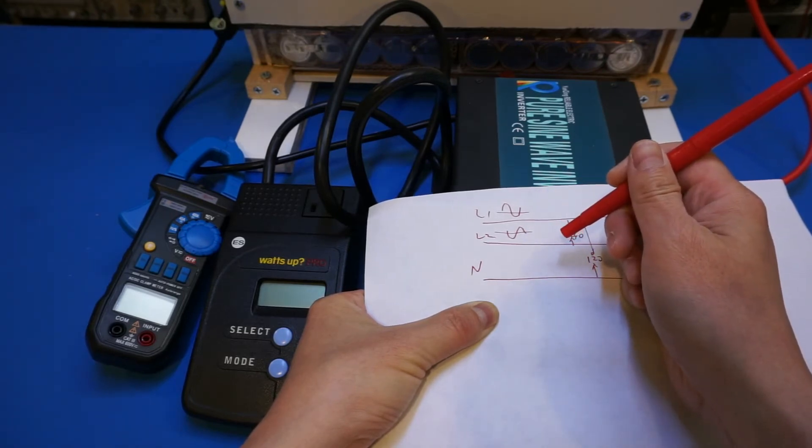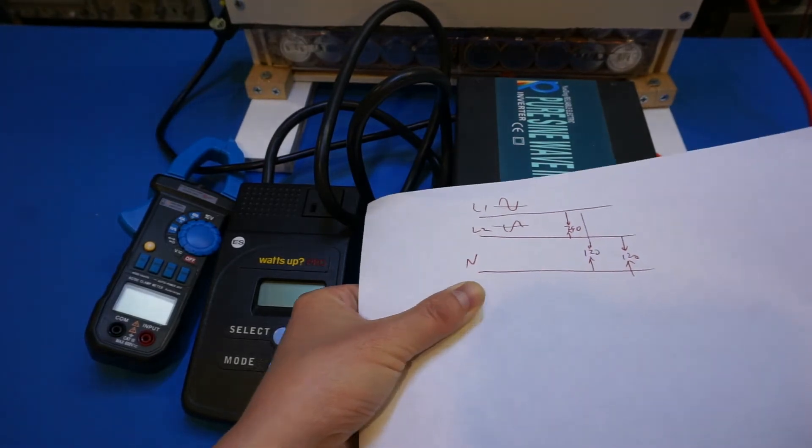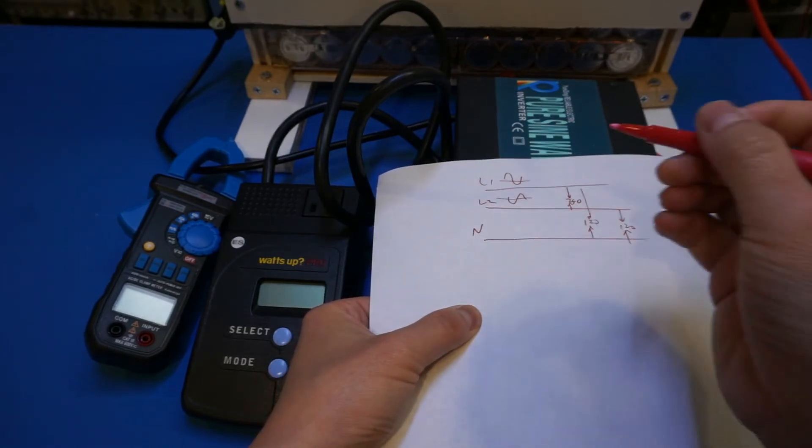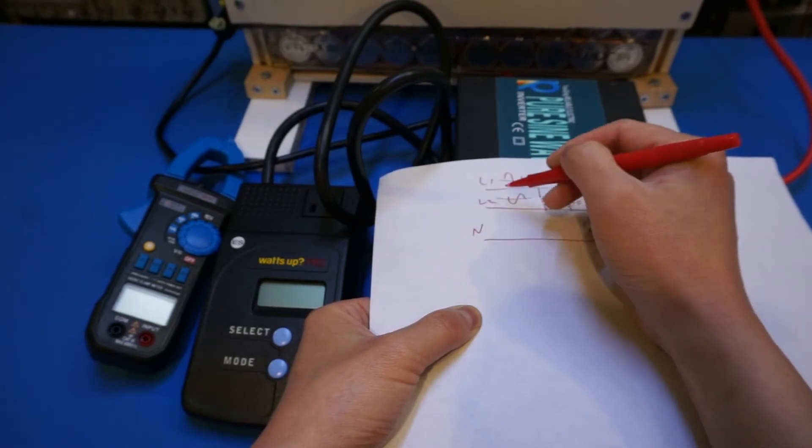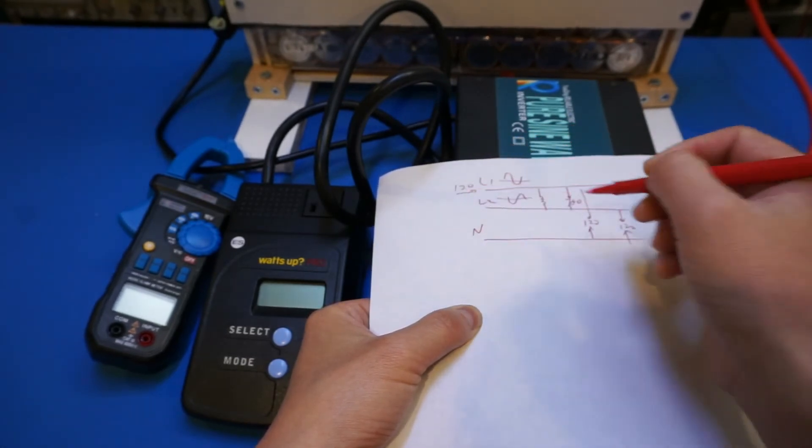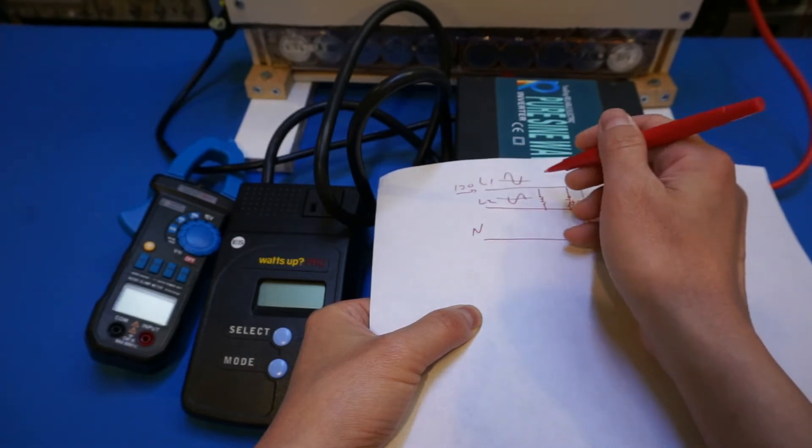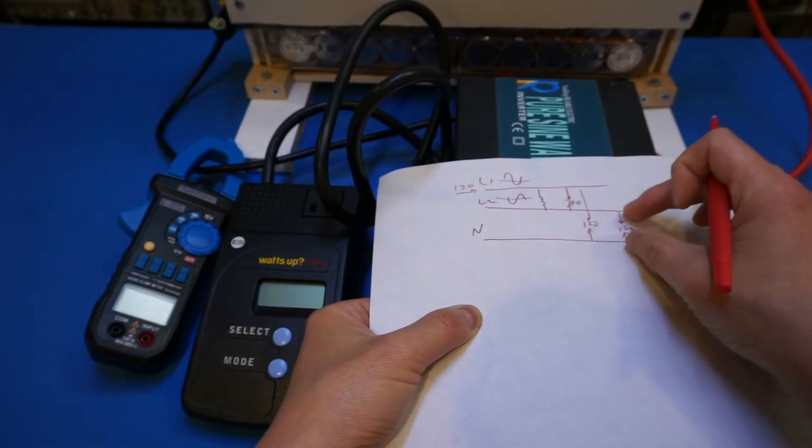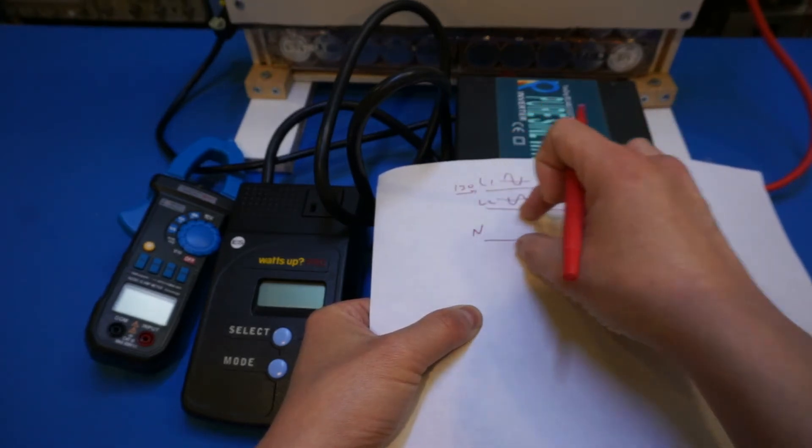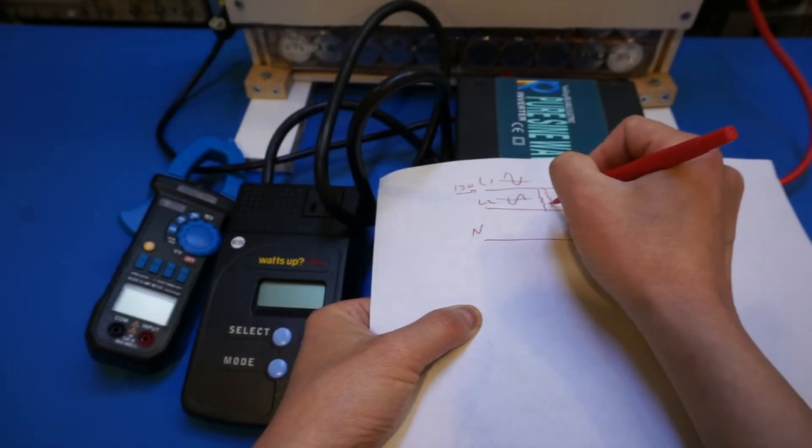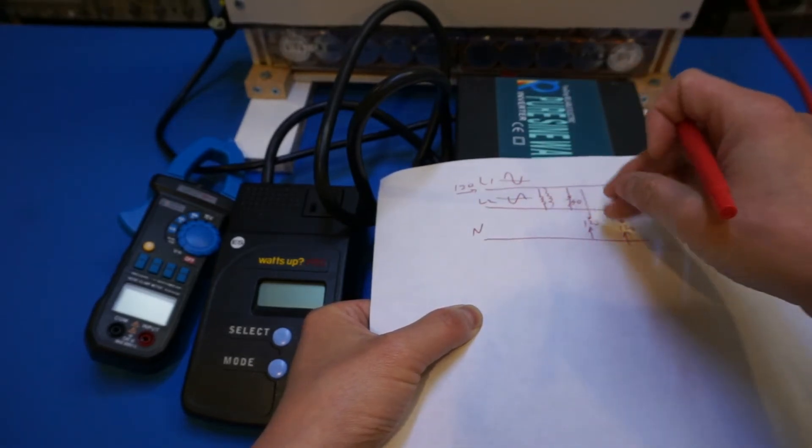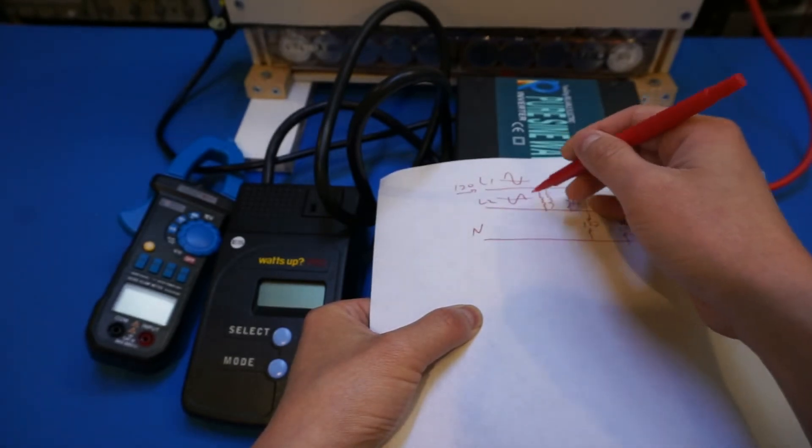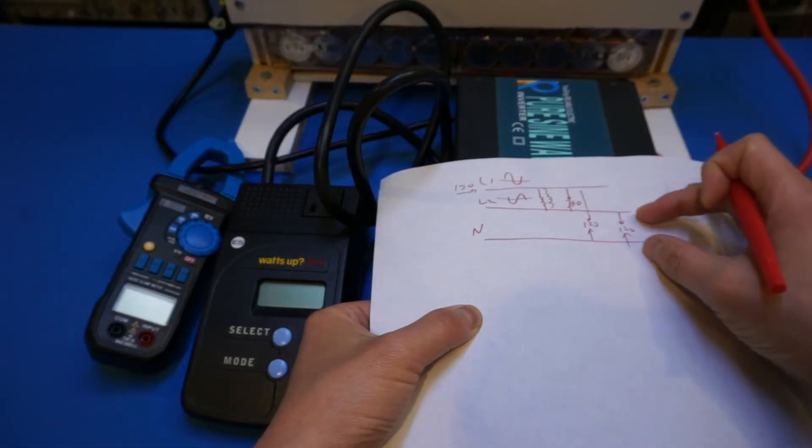Now that said, you cannot just power a single phase and leave the other one floating. The reason is that because you might have appliances, let's say a heater, connected between these two live wires. And let's say if you are only powering L1, this is 120, this is neutral, then what happens, you're going to have a voltage that's passing through this resistor appearing on L2. And when you have other devices connected to the second line, you will experience brownout. And worse yet, if there's some inductive load here, let's say a motor or something, then you will have weird voltage waveforms appearing on this second line and potentially going to create some dangerous voltage spikes and might even damage your connected devices.